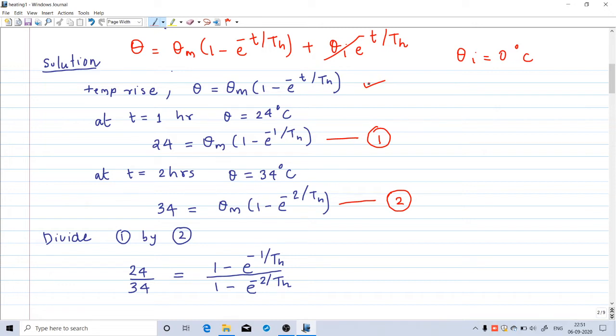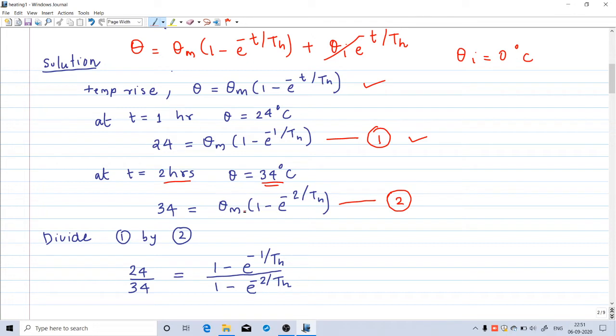Using the given information: at t equal to 1 hour, temperature rise is 24 degrees Celsius, so 24 equals theta_m into (1 minus e raised to minus 1 by th) — that is equation 1. At t equal to 2 hours, temperature rise is 34 degrees Celsius, giving equation 2: 34 equals theta_m into (1 minus e raised to minus 2 by th). We now have two unknowns, theta_m and th, and two equations.